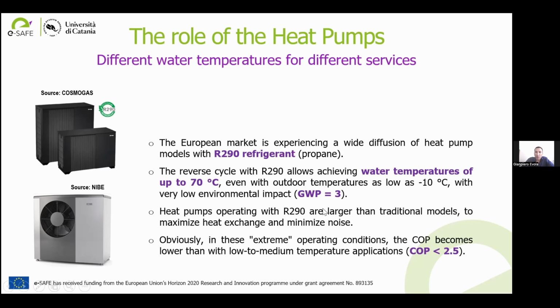It has a global warming potential of only 3, so very low, and it has a very interesting feature. It lets the heat pump work even with very high water temperatures, up to 70 degrees C, which in normal heat pumps with common refrigerants is not possible.